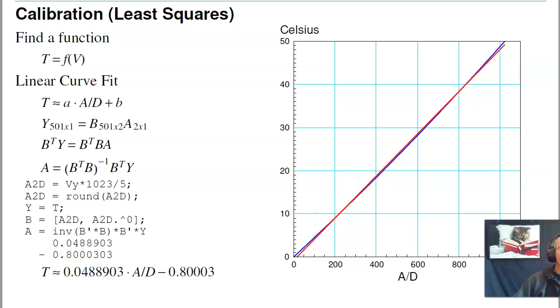Put that in matrix form. So my basis is the A to D reading and 1. To solve for A, it's going to be B transpose B inverse times B transpose times Y. It's going to be this line of code. There's my curve fit. It says the temperature is 0.0488 times the A to D reading minus 0.8. If I plug that in, I get the red line. Notice it's a little bit different. That's my calibration error.